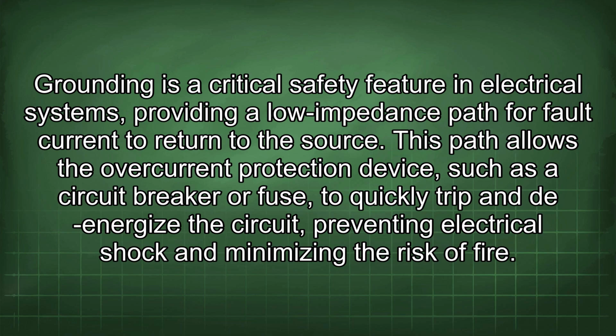Grounding is a critical safety feature in electrical systems, providing a low impedance path for fault current to return to the source. This path allows the overcurrent protection device, such as a circuit breaker or fuse, to quickly trip and de-energize the circuit, preventing electrical shock and minimizing the risk of fire.